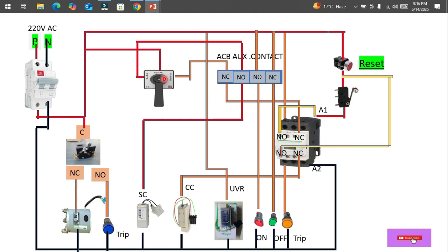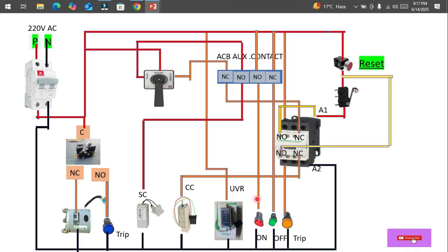Once the fault is cleared, we turn the TNC knob toward the close side to switch the breaker back on. When we turn the knob toward close, the phase travels through the NC contact of the auxiliary contact of the air circuit breaker. This is interlocked with the trip contactor, so the phase goes through this NC contact — which is NC only when there is no fault and the contactor is de-energized.